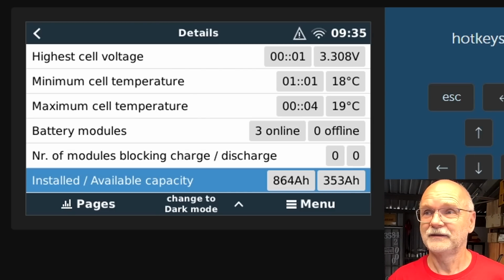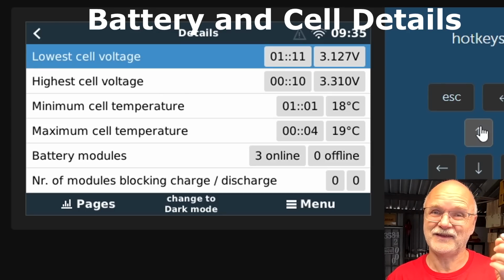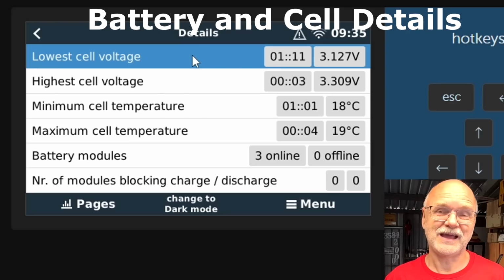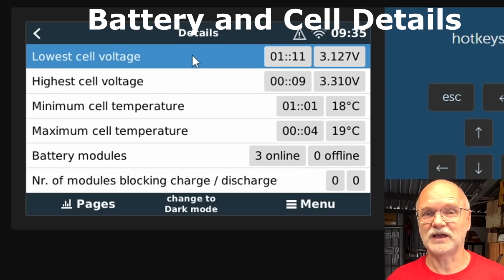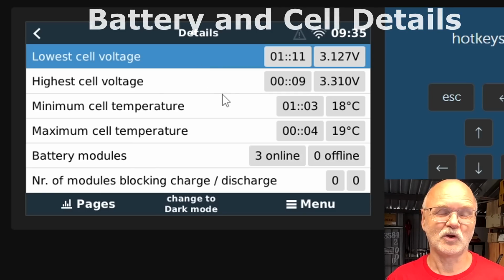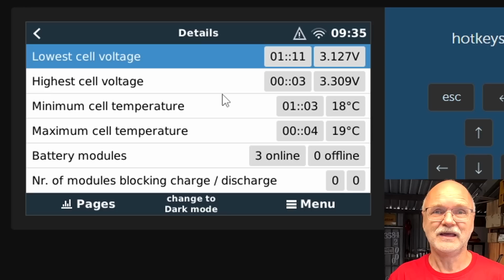While we are in here, you can also see it shows the highest and lowest voltage cell as well as the highest and lowest temperature cell, but we didn't know in which module, in which battery this actually was. It always showed the information only for the master BMS, but now we've got the information for module 0, which is our master, slave 1, and there's also a slave 2, which is not showing up at the moment because the lowest and highest temperature and cell voltages are occurring only in these 2 batteries.